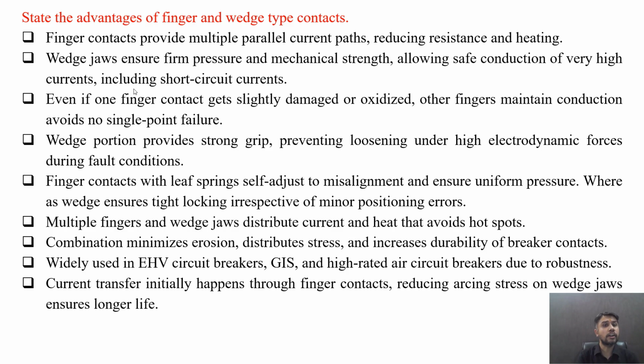Even if one finger contact gets slightly damaged or oxidized, other fingers maintain conduction, avoiding a single point of failure. The wedge portion provides a strong grip, preventing loosening under high electrodynamic forces during fault conditions. Finger contacts with leaf springs self-adjust to misalignment and ensure uniform pressure throughout, whereas the wedge ensures tight locking irrespective of minor positioning errors. Multiple fingers and wedge jaws distribute current and heat, which avoids hot spots.